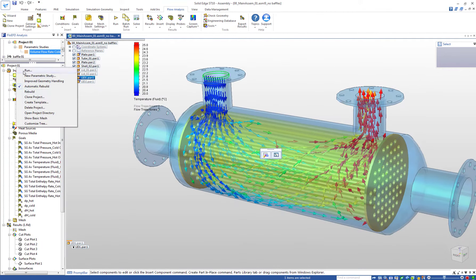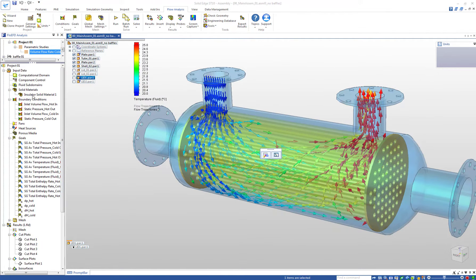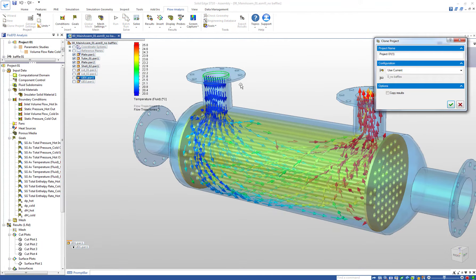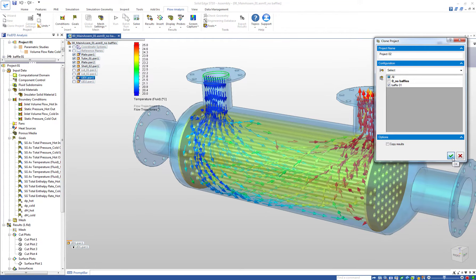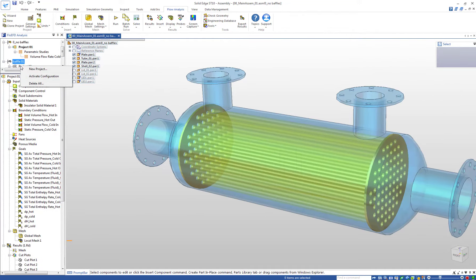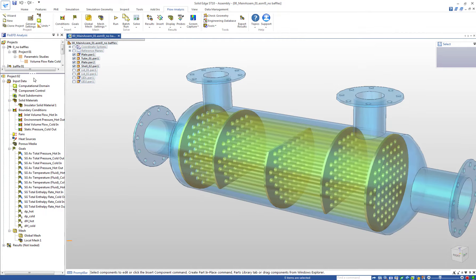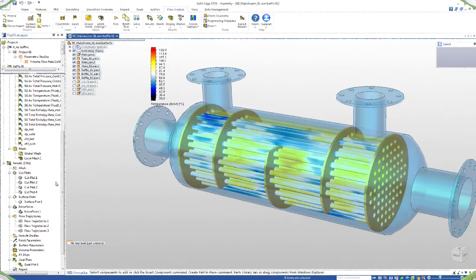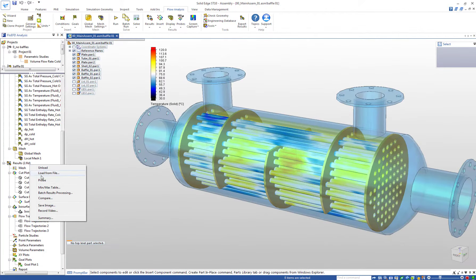We use the clone function to set up a copy of our project, and we can activate the second configuration that contains some additional baffles to change the flow path through the shell side.